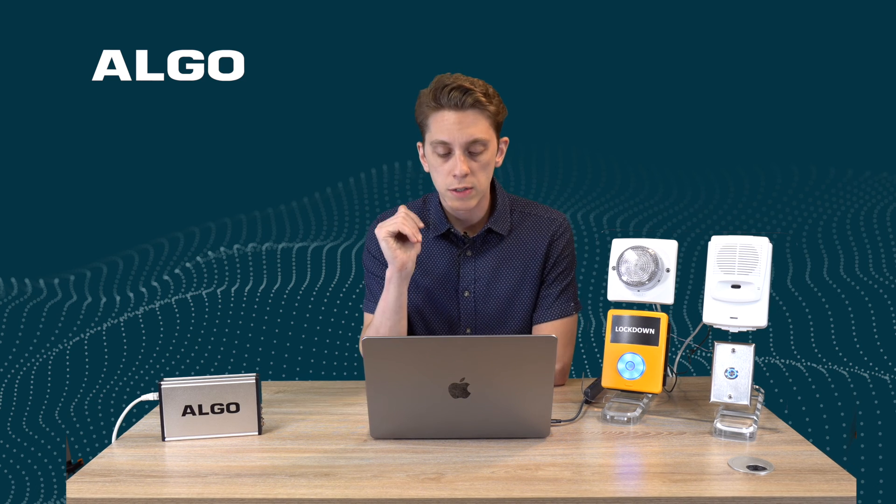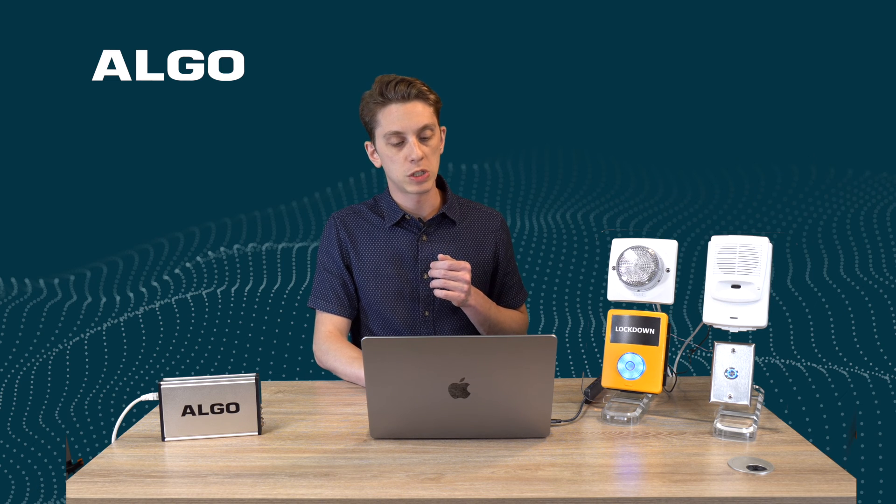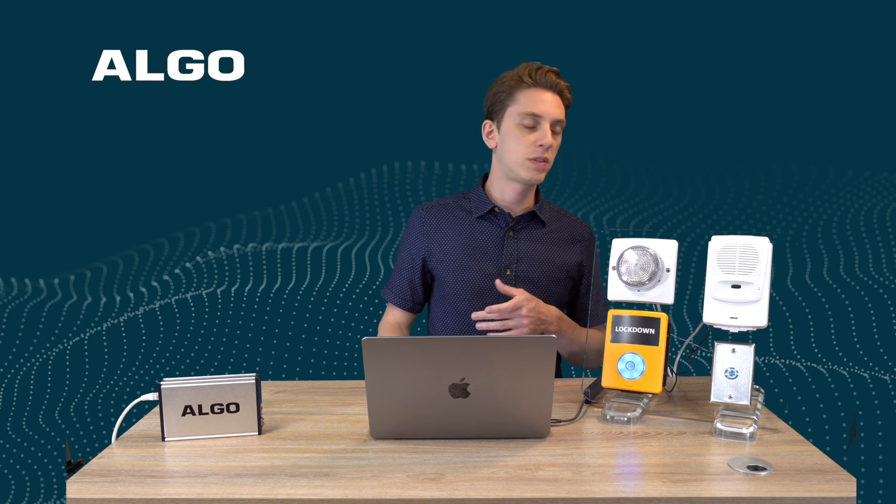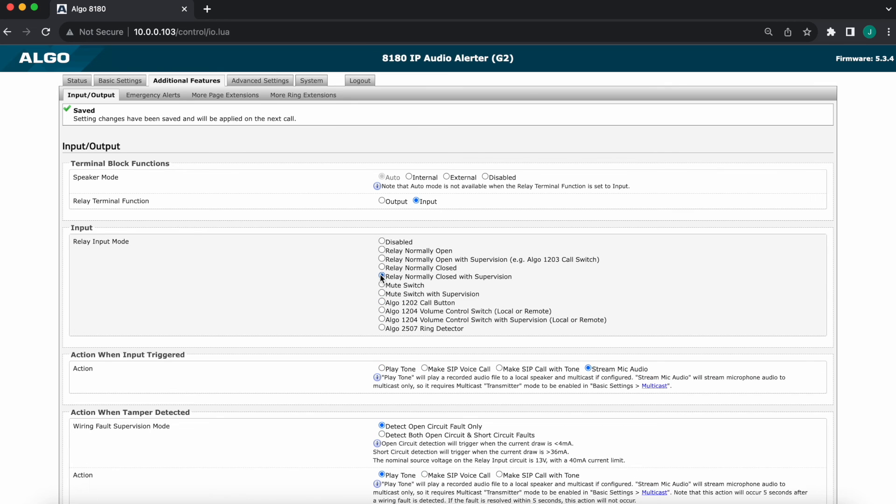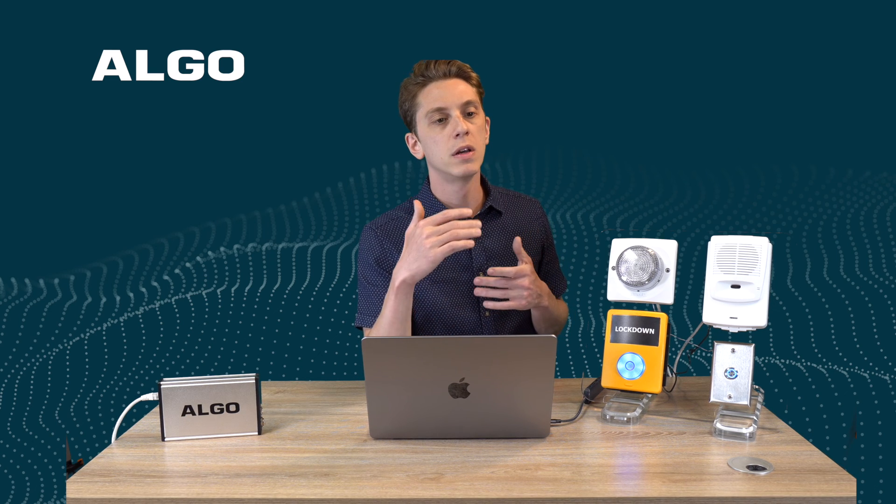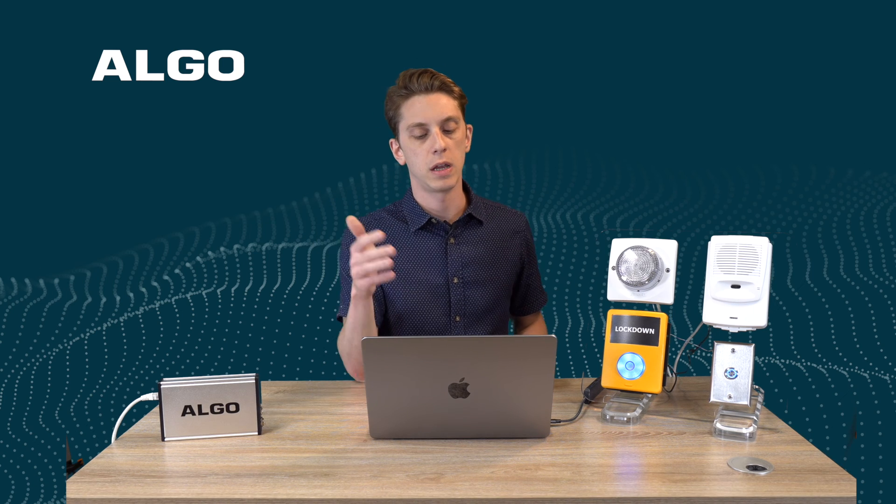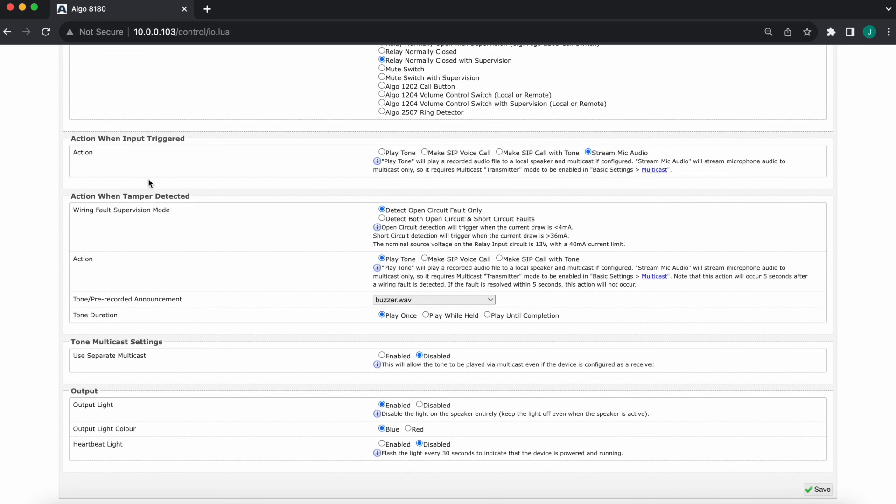Last but not least, supervision is available in certain modes and basically supervision lets you select an action when tamper is detected. So tamper would basically mean, for whatever reason, this accessory device is no longer reachable. The host device in that case, the 8180, cannot reach this device here. Let's say cables were severed for whatever reason, something happened. This would qualify as a tamper and then you can pick an option as to how the wiring fault supervision mode will take place, what action will take place when the tamper is detected and so on.